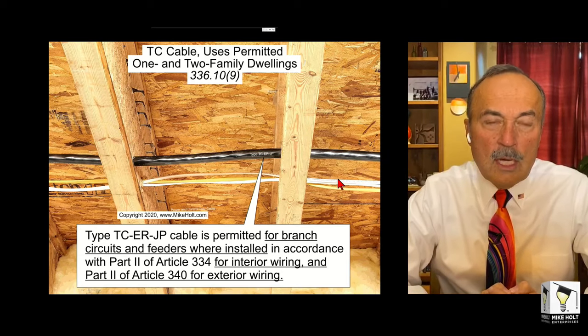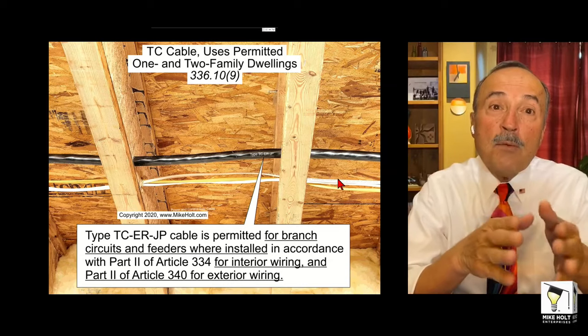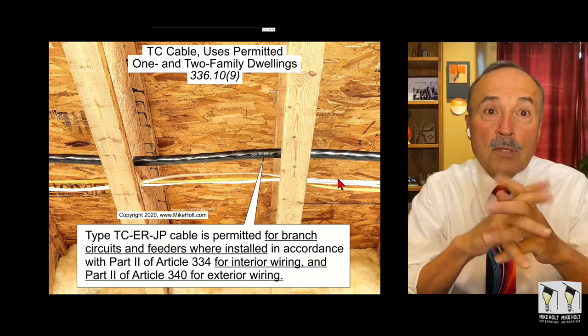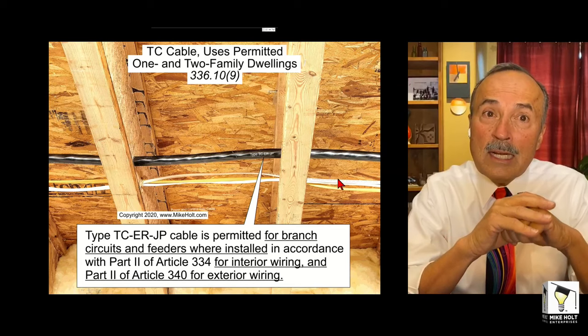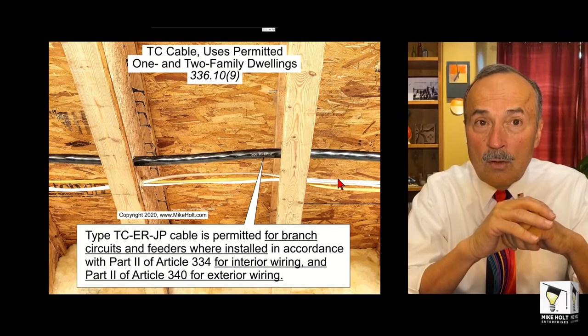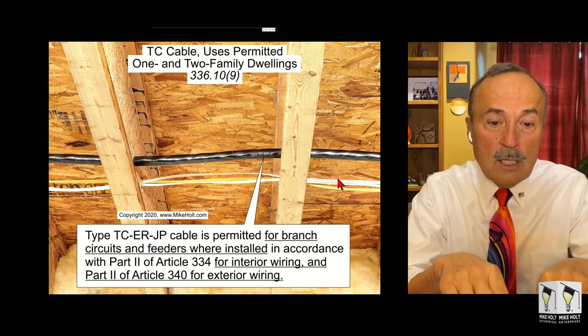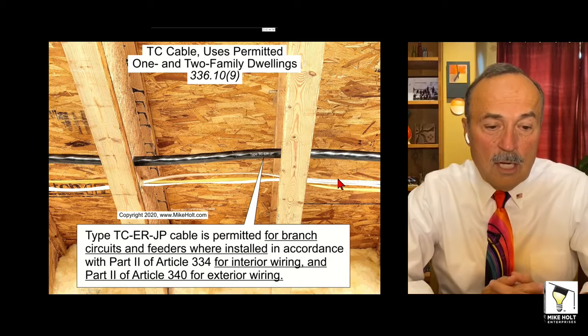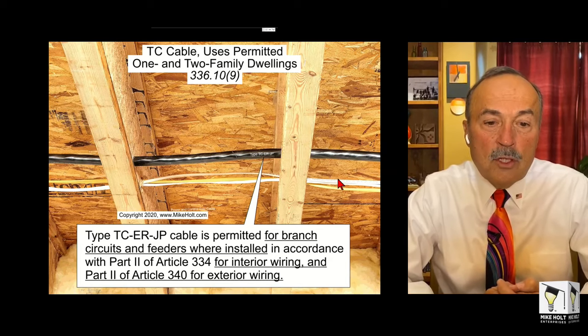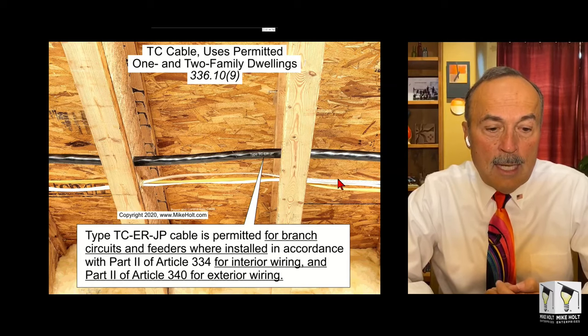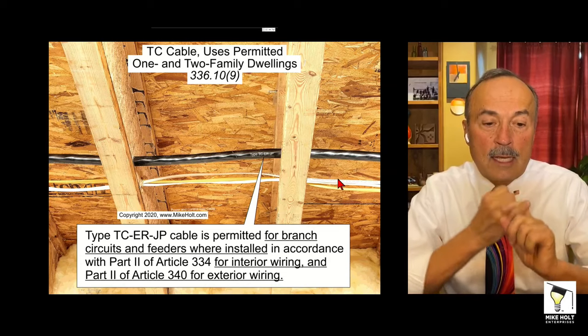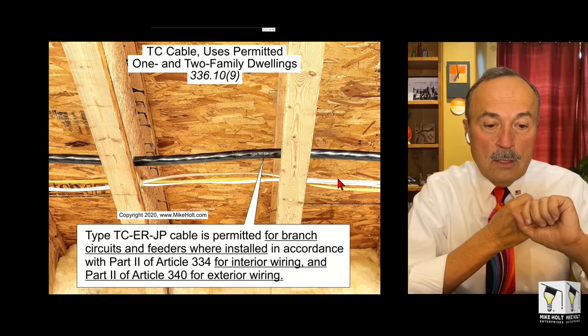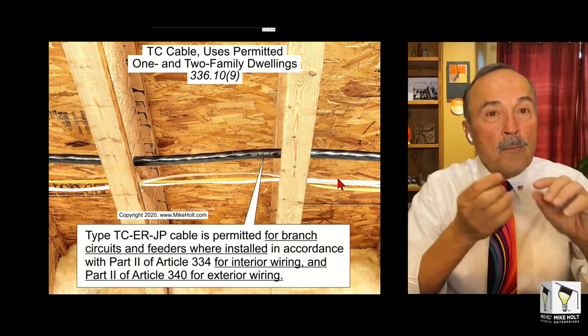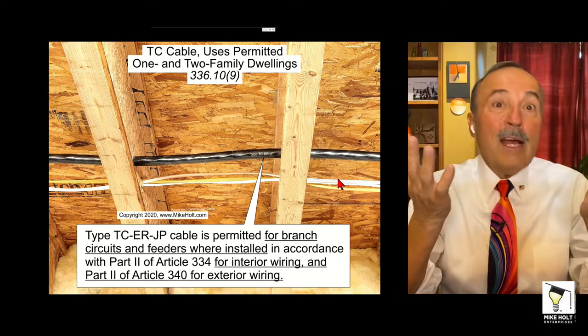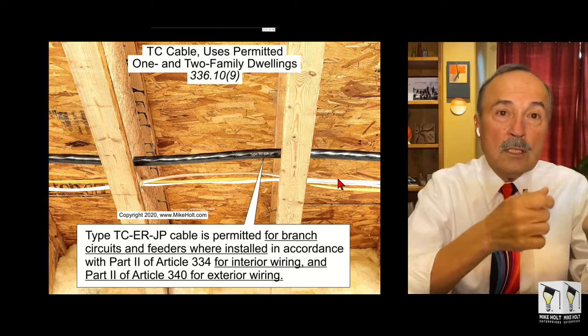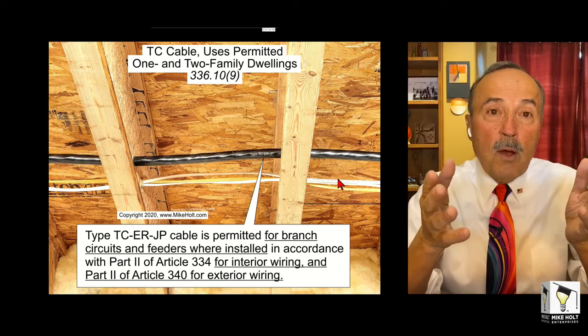Now, tray cable can be used in a lot of locations. Even though they came up with this product, I said, guys, you can't use that product. I'm saying, no, you can't use that product because it's not recognized as suitable by the National Electrical Code. I think it was the 2017 code that modified this to recognize this language here, and it was revised again for the 2020 code. Here's what it says. Title: TC cable uses permitted, one- and two-family dwellings. Type TC-ER-JP. Let's see, that's tray cable, exposed runs, joist pull. See, Romex has been around for 100 years, and we know that you pull it through joists, and it can be run exposed.